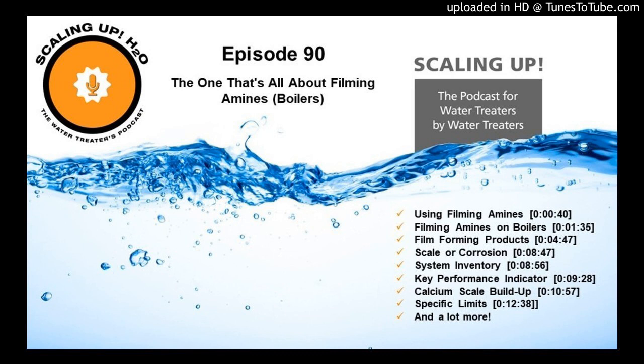So you're going to watch your iron level climb, and we're just going to hold steady with that dosing rate. And then we're going to blow it down, blow it down, blow it down. And then we're going to start to watch the water clear up. We're going to watch the iron level start to drop. And as it starts to drop, as our iron numbers improve, we're actually going to increase our dose. So if we were at a quarter of the theoretical loading at 250 parts of product, we're going to bump to 500. Or if we were sitting happy at 500 and we start to see the iron number come down, we're going to bump to 1,000.